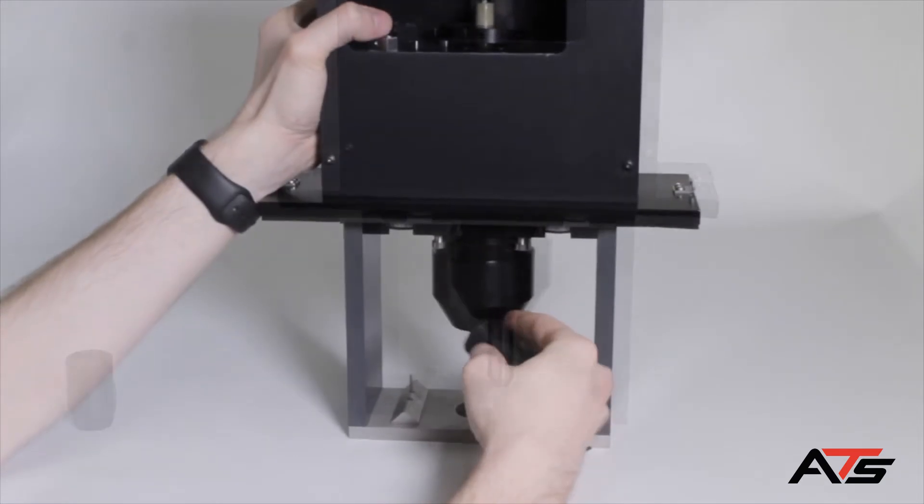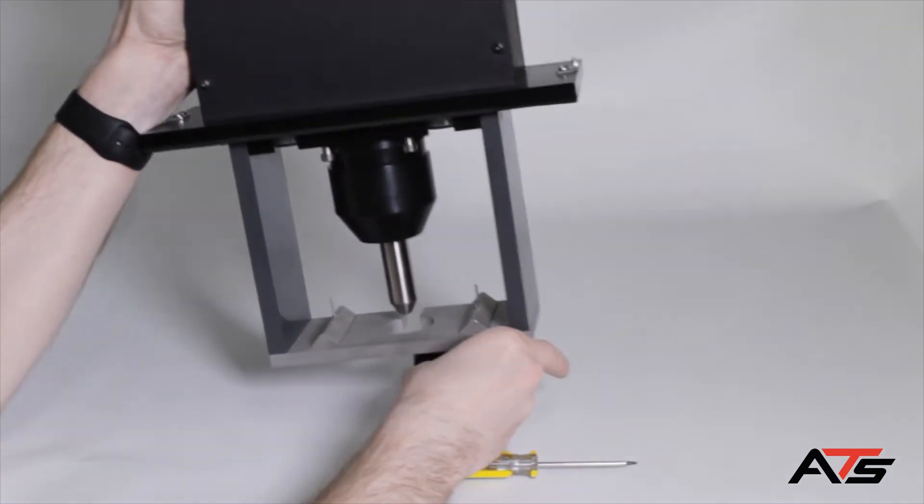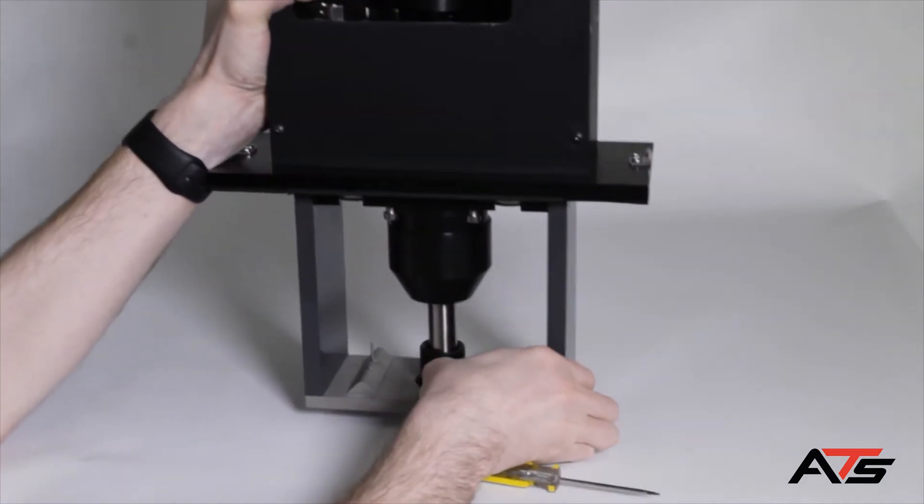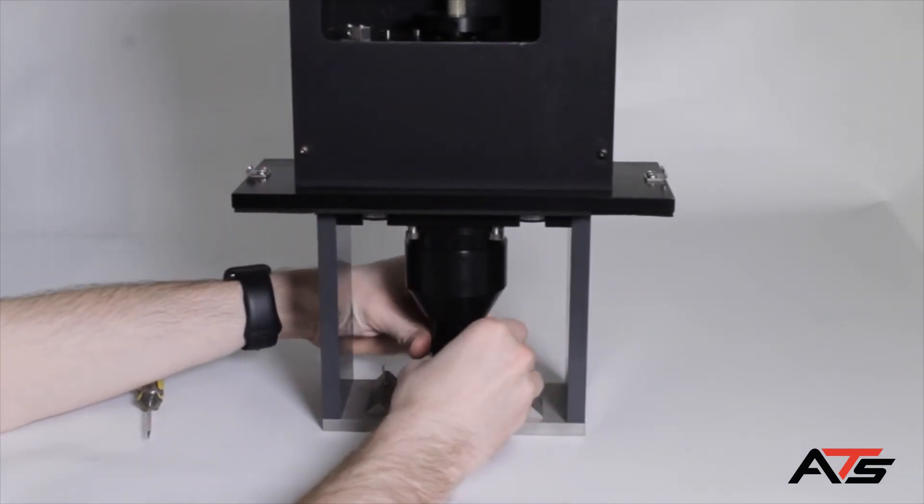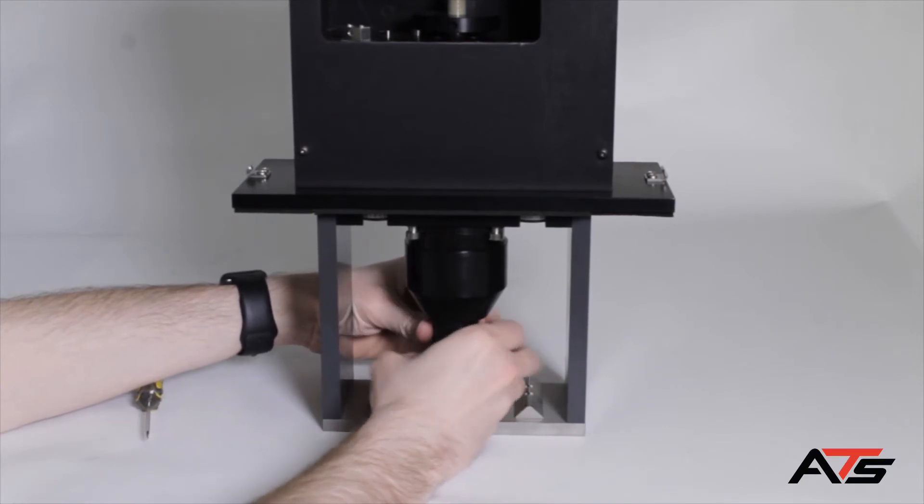To reattach the lower portion of the load shroud, carefully lift the load frame and position it so the load nose is directly above the lower portion of the shroud. Lift the lower portion of the shroud up and gently screw it into the upper portion.